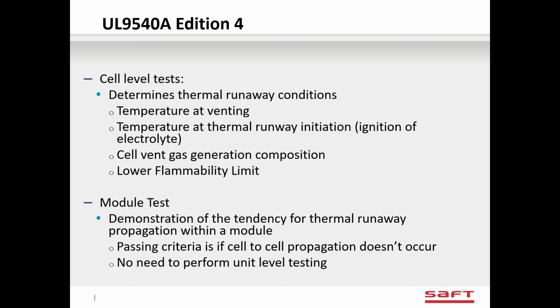Once they know how to do it, they proceed to the module level test. And what they're looking for here is to see if you get cell to cell propagation. And with our iron phosphate, we did not get any cell to cell propagation beyond what we forced with the heaters. So that one cell that we got to go into thermal runaway did not heat up enough to cause another one next to it to go into thermal runaway.